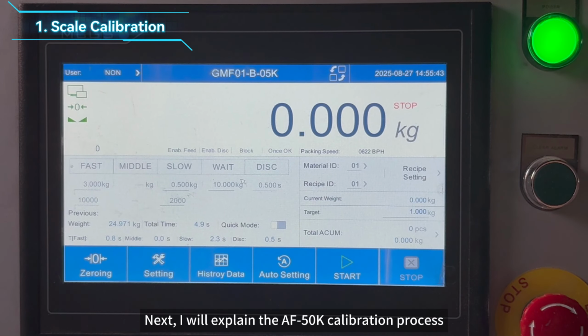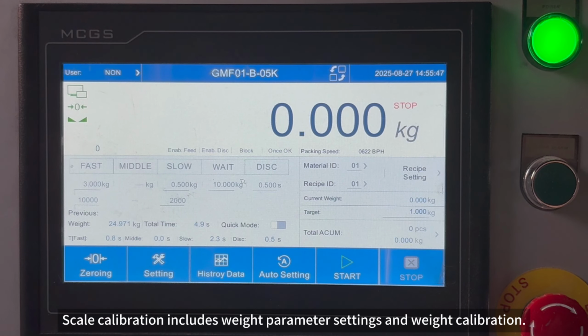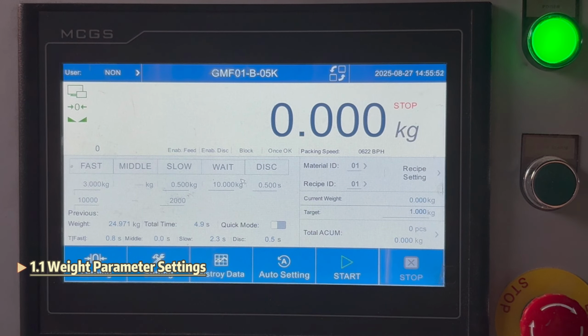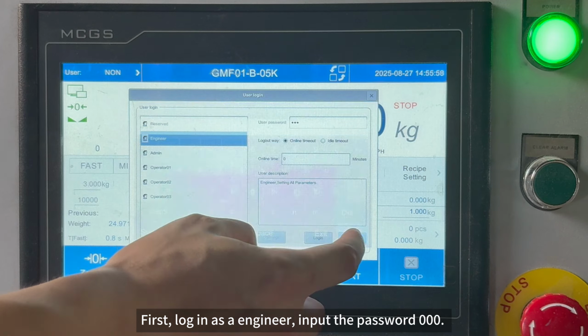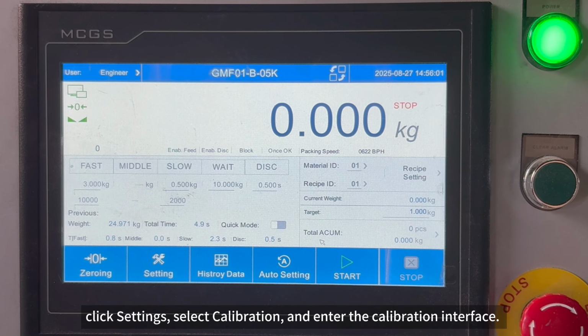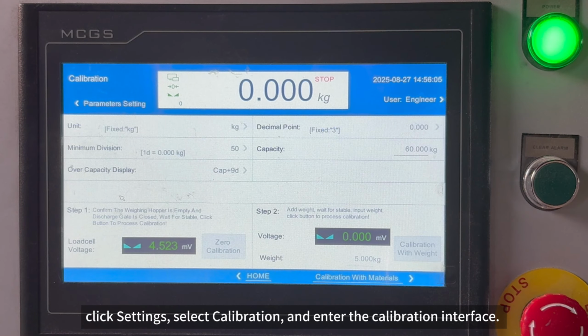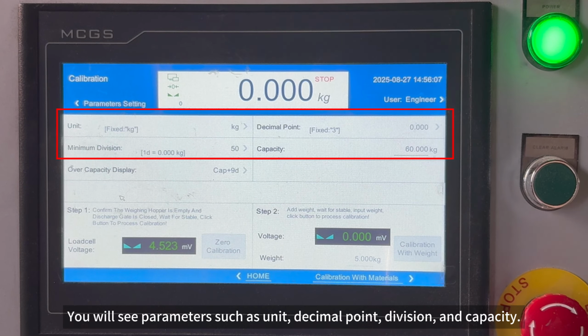Next, I will explain the AF-50K calibration process. Scale calibration includes weight parameter settings and weight calibration. 1.1 Weight parameter settings. First, log in as engineer. Input the password 000. Click Settings, select Calibration, and enter the calibration interface. You will see parameters such as unit, decimal point, division, and capacity.